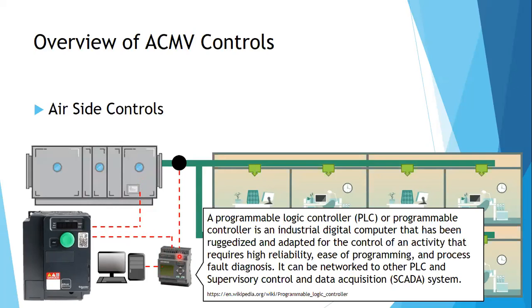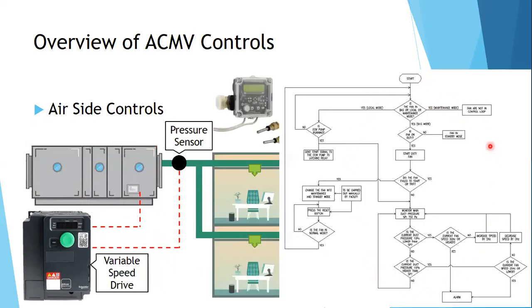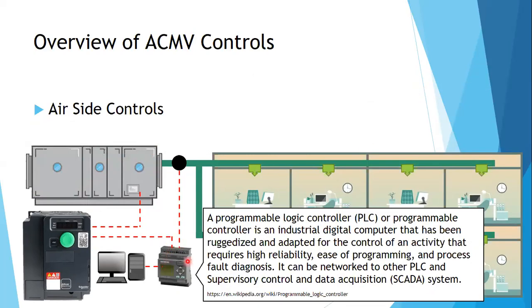Sometimes this PLC has an option to bring out the signal or to show the display to a remote area, to a remote computer. So this remote computer only shows the display or only has remote access to a PLC. This remote access, we call it supervisory control, or sometimes we call it a SCADA system. So a lot of PLCs can go to a single remote unit. It's called a SCADA system. Again, the control of an equipment starts with your control logic. This control logic is housed inside a PLC. This is the heart of your control now, your PLC. This PLC monitors your devices and gives appropriate action to other devices so that your set point will be followed.